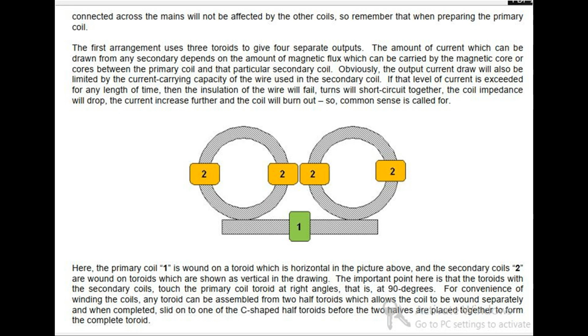The first arrangement uses 3 toroids to give 4 separate outputs. The amount of current which can be drawn from any secondary depends on the amount of magnetic flux which can be carried by the magnetic core or cores between the primary coil and that particular secondary coil. Obviously, the output current draw will also be limited by the current carrying capacity of the wire used in the secondary coil. If that level of current is exceeded for any length of time, then the insulation of the wire will fail, turns will short circuit together, the coil impedance will drop, the current increase further and the coil will burn out, so common sense is called for.